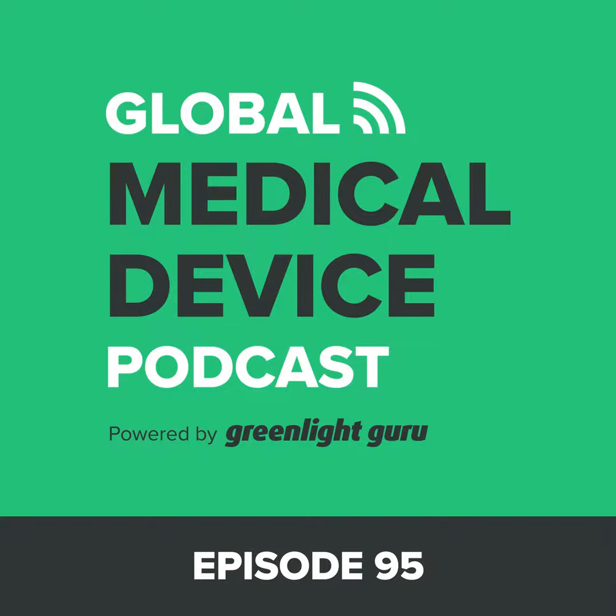However, if you've had a device that's been on the market for a while, it's approved, and you're changing something in the internal mechanism, like the computer board that runs it, and there's no change to the device user interface, then technically you don't need to do a human factors update, because you're already approved and you're not changing that basic user interface.